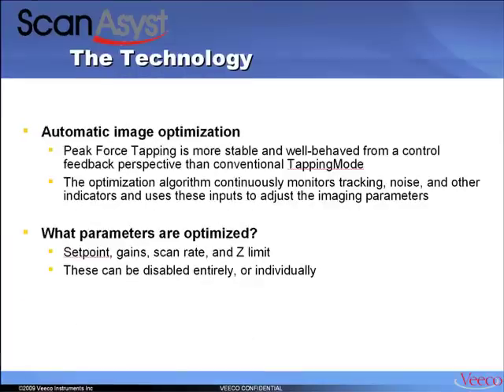Automatic image optimization is, of course, a game-changer. Peak force tapping is a much more stable method from an image optimization perspective than conventional tapping mode. This has to do with the fact that in peak force tapping we actually measure forces directly, whereas in tapping mode we monitor a gradient change by measuring a change in amplitude. The optimization algorithm continuously monitors the quality of tracking, the noise on a scan line, and other parameters, and uses these inputs to adjust the imaging parameters — set point, feedback gain, scan rate, and the limit. If you desire, you can disable the optimization entirely or individually and change these parameters by hand.